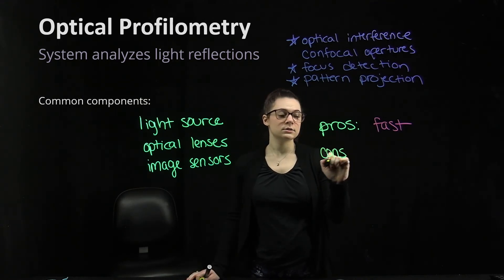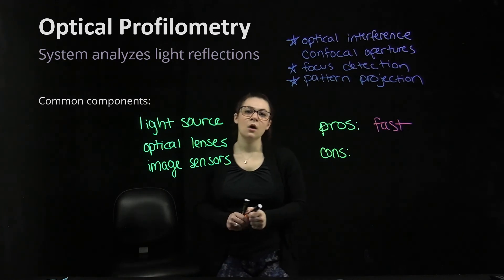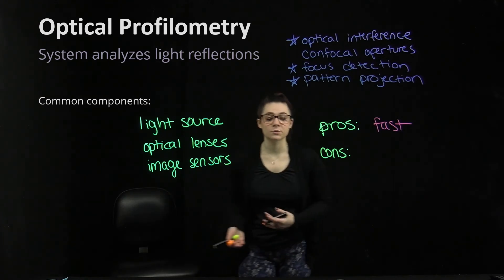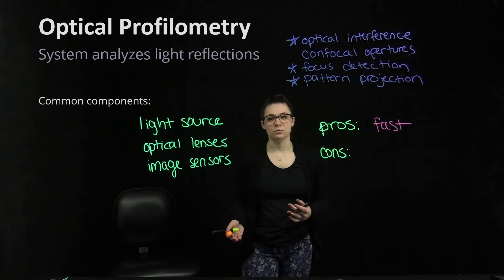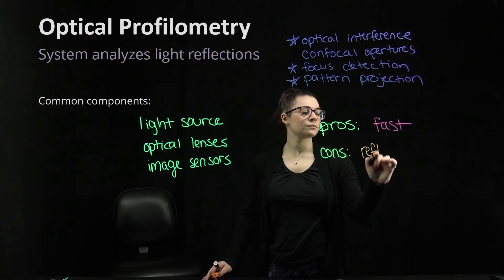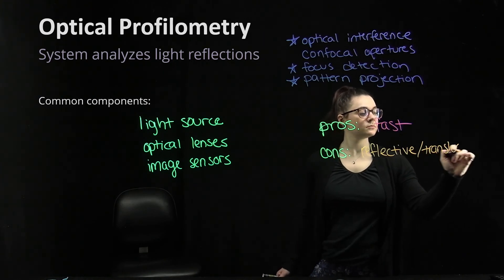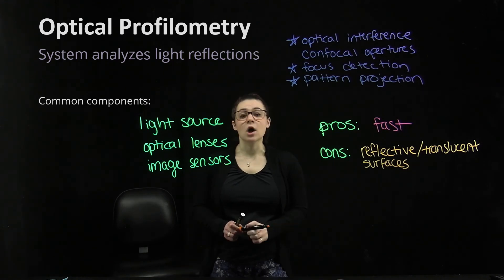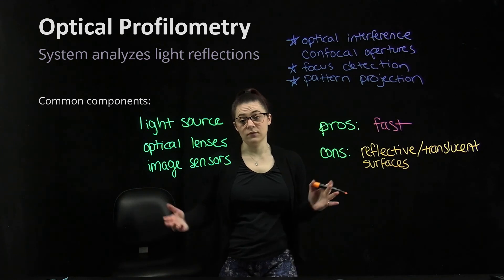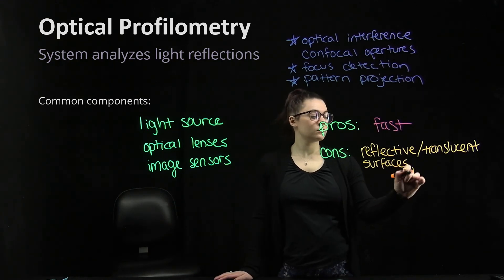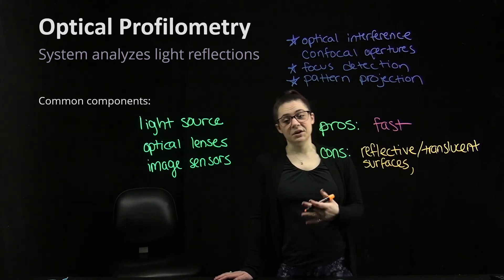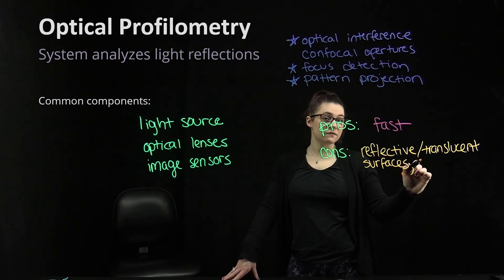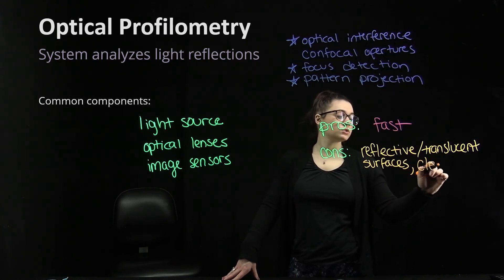The main cons are that optical profilometry has difficulty with reflective or translucent surfaces — unlike stylus profilometry, the optical properties of the material do matter here. If the system can't determine where the focus is, it can't determine how the surface morphology looks. We also need a very high level of cleanliness, as any piece of dirt or imperfection will affect the measurements.